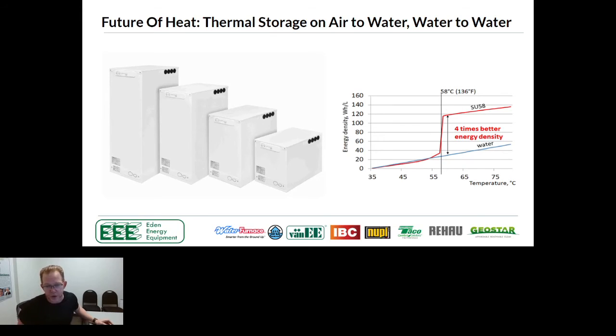A great example for this technology is I have a customer, I'm not sure if he's on the training today. He was faced with retrofitting his commercial building, $600,000 to take out his electric heat for his domestic and go CO2. He called me for suggestions, and what I had proposed to him is let's do this instead, right? So at the end of the day, we can store 300,000 BTUs in a 4-foot cube, and his cost on that was like 40 grand. So we're talking 600,000 or 40 grand. He's keeping the electric because what he's going to do is he's going to charge the battery off peak. The apartment building will charge off the battery on peak. So where I'm going with that is don't assume that these solutions are more expensive. You just don't know that without looking.